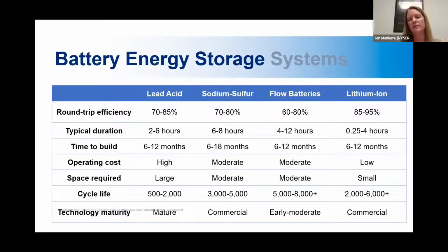I mentioned before that lithium ion is sort of dominating the market at this point, and try not to get too overwhelmed with this chart. I realize there's a lot on there, but it's essentially just showing why lithium ion is dominating now over some of the other potential battery types. So just starting on the top row there, they have a pretty high round trip efficiency. The duration, the amount of energy they can store, like how long they would be able to push energy out for, is maybe not quite as long as some of the other types, up to about 4 hours or so. And they can even be more than 4 hours too, but this is typical. A little bit less, but still a pretty good duration. You don't often need it for too much more than that.